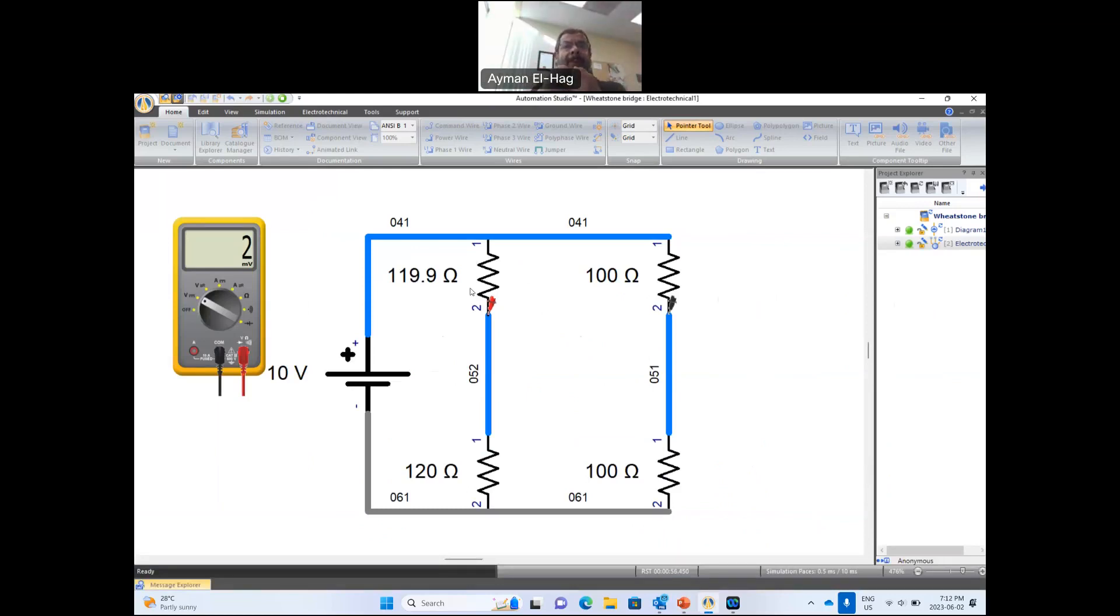Now, if you apply a tensile force on the strain gauge, this resistance will increase, but it will not increase to a very high value, to a small value like about 0.1 ohm. If you apply a compression force, then you will have a small reduction in the resistance. Now, that change in the resistance due to the force is reflected as a change in the voltage.